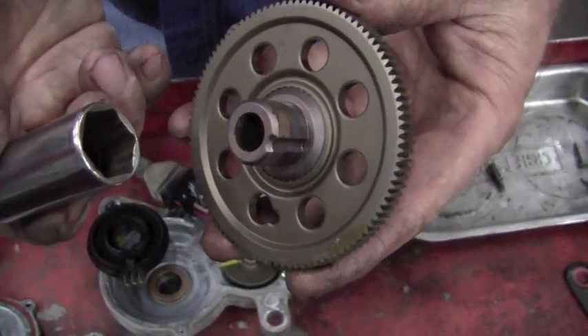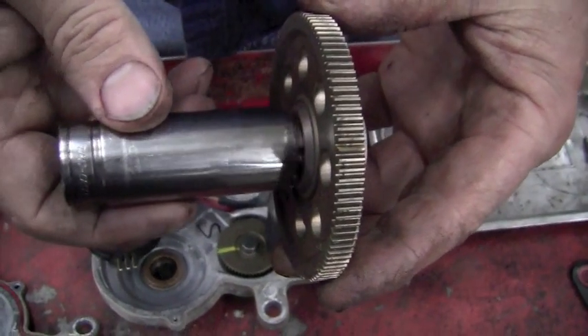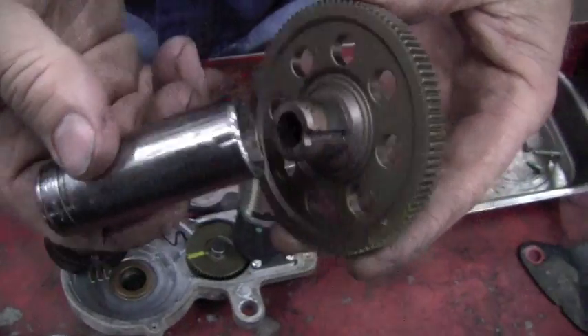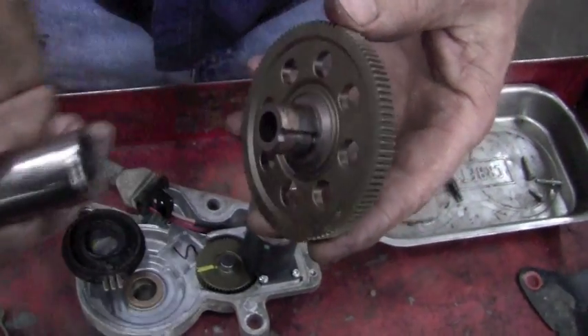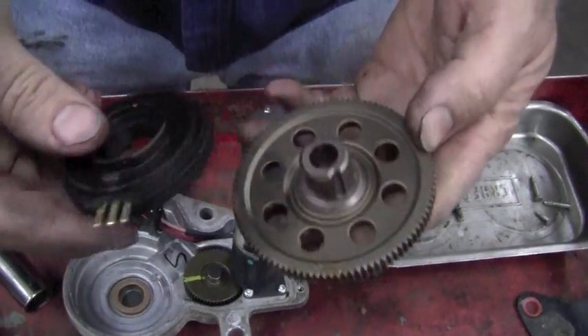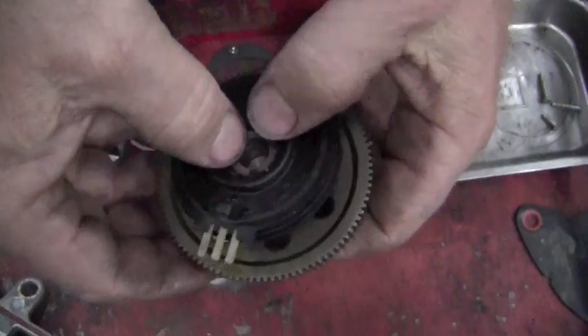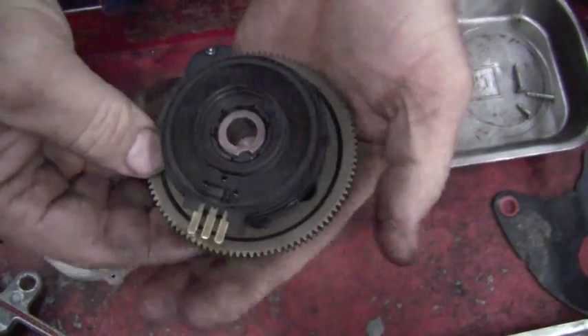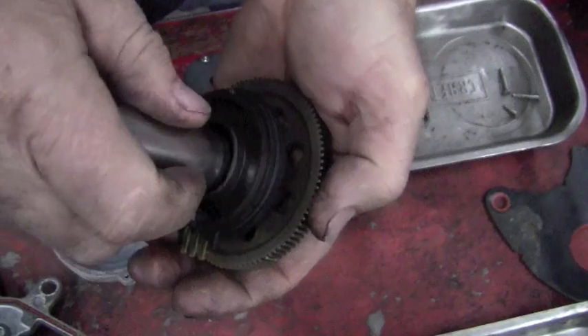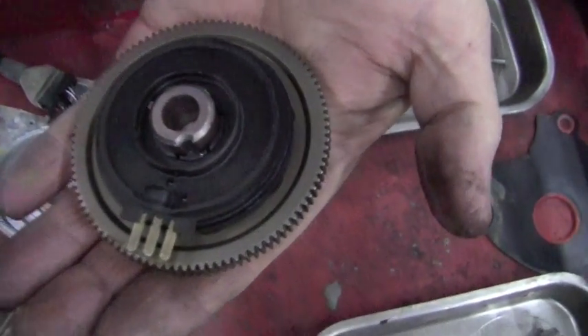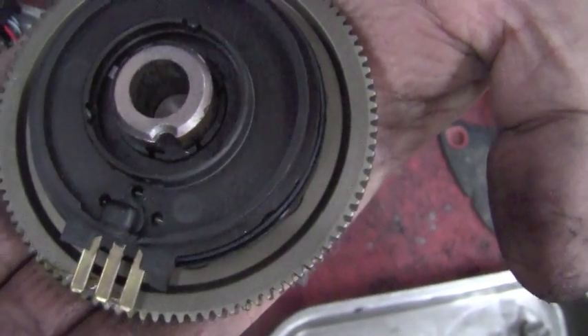Now you want to make sure you don't damage the sensor when you put it on, so take a 3/4 deep well socket that'll fit over that, and that's how we'll install the sensor. Line up your keyway and just begin to push it on, don't force it, so you don't damage the inside plastic part of that sensor.